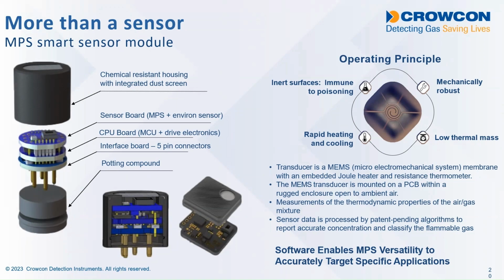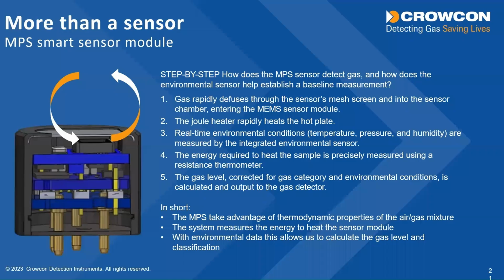They're mounted on a PCB within a small sensor housing, and there is a gauze that enables air to enter the sensing chamber. And as I said before, it's constantly measuring the thermodynamic properties of the air to which it's exposed. So air can diffuse into the sensor through the gauze and comes into contact with the MEMS sensor module, and then there is a joule heater that's rapidly heating up the MEMS sensor plate. It heats out to about 900 degrees Celsius every 2 seconds, so it's able to heat up and cool down again to 900 degrees Celsius from ambient every 2 seconds.